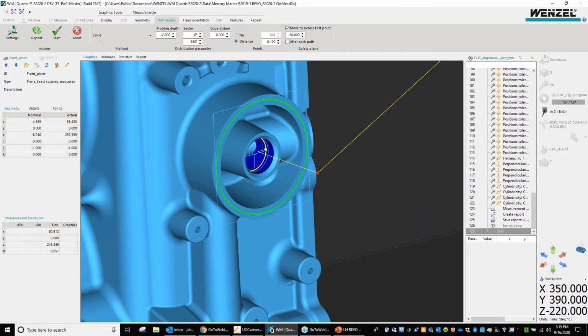What controls do I have here? Well, I have the depth of measurement here, so it's just a matter of using the up and down arrows to adjust the depth. And then the sector: how much of this circle would I like to measure? I'm going to start at 0 and go all the way around 360. And then here I also have the desired number of points, either the number of points that I want to come back into Quartis for calculation, or a distance between each point. So as I move down, the more points I can collect. And the other thing I have in here as well is the safety plane. So this is going to keep the probe away from that object at this value, 50 millimeters.